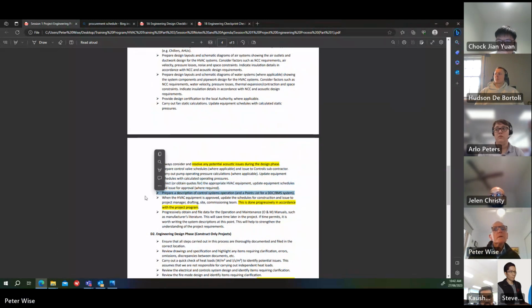It's good to prepare a description of the controls of the system. Remember, we're in the design and construct phase, so we're driving the design and how the systems are going to be controlled. You need to prepare a description of the controls, which will then go on to the controls subcontractor. It helps, if you've got a BMS system, to do a points list - all the points that need to be controlled and how they're controlled, the digital outputs, digital inputs, etc.